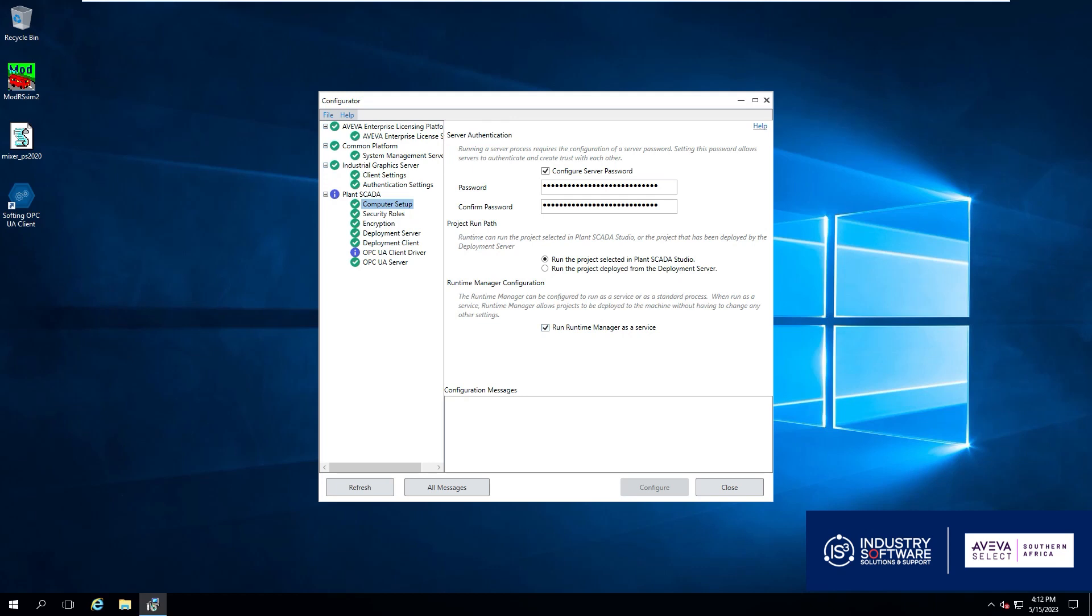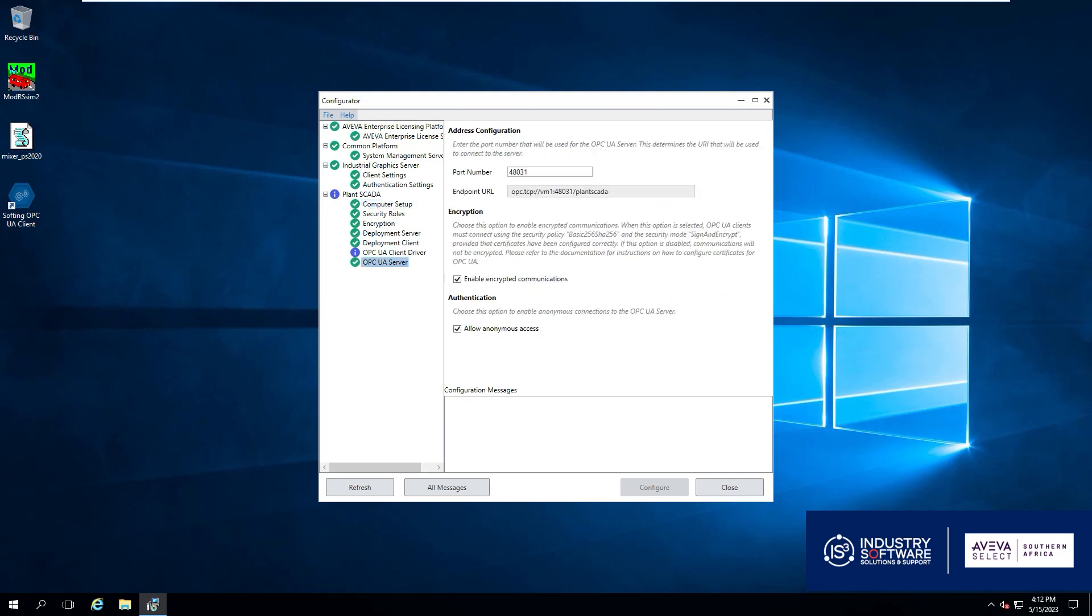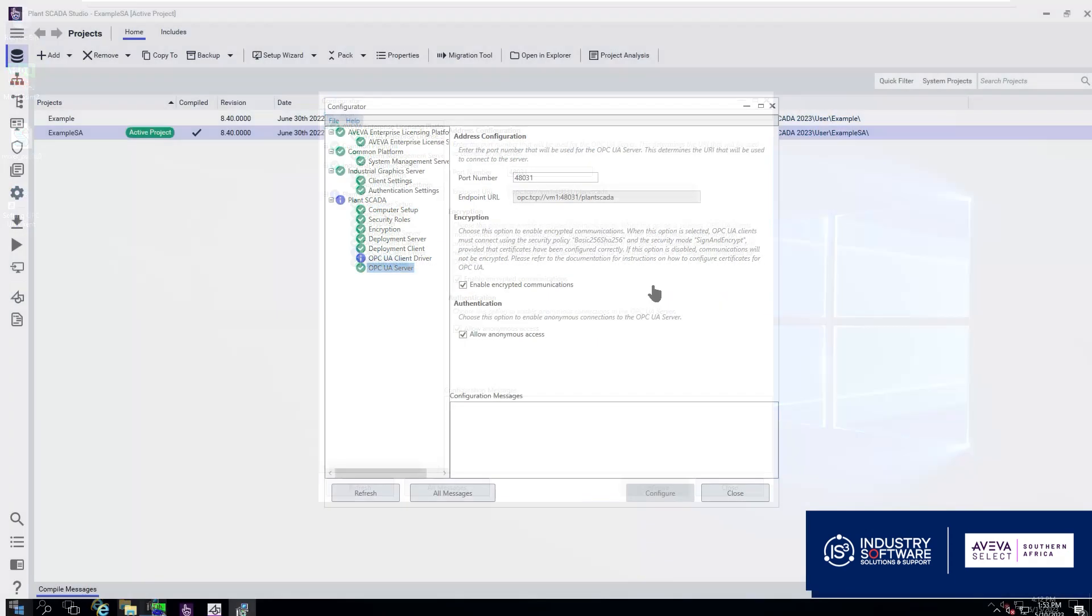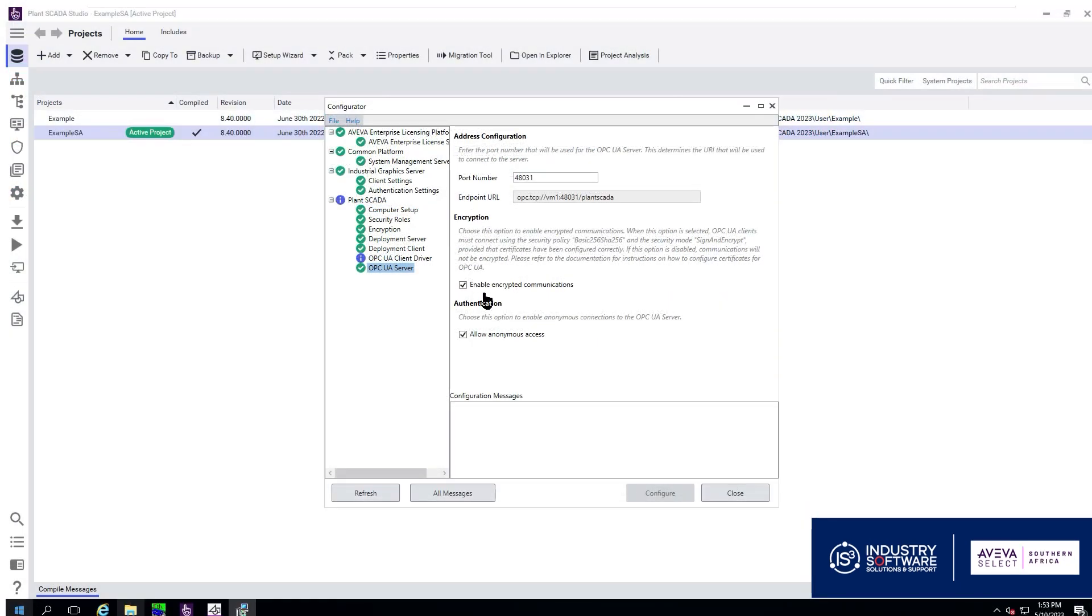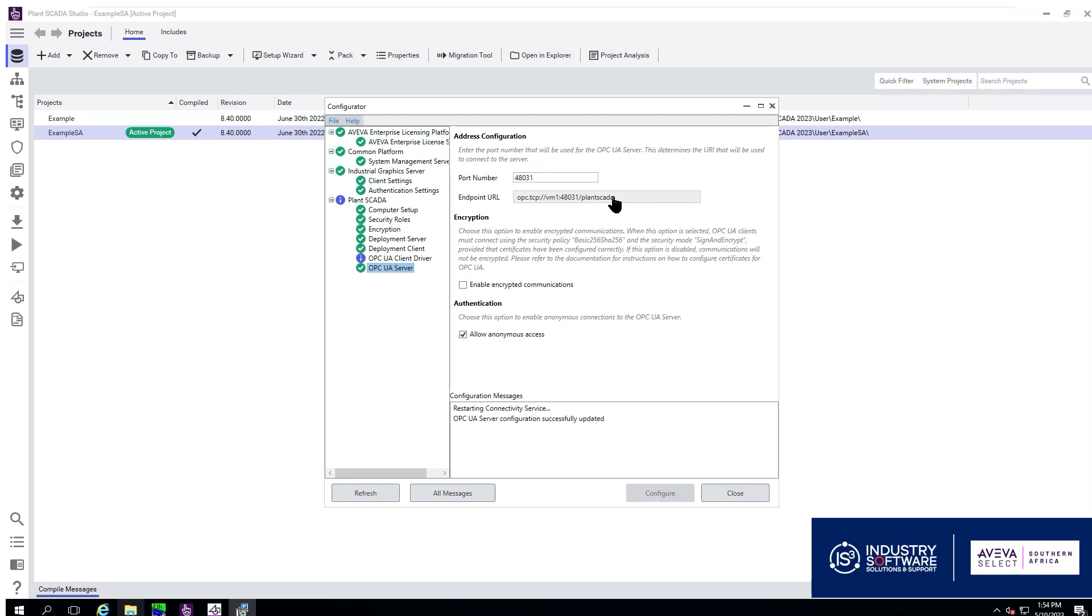We want to confirm that our runtime manager is set to run as a service and then go over to our OPC UA server config. We are going to be using a standard anonymous access so we are going to remove enable encrypted communication and copy the endpoint URL.